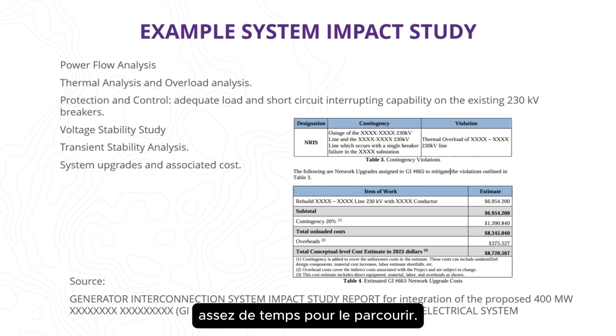I did mention IEEE 1547 and IEEE 2800, for those of you who are members of IEEE. If you're not, I urge you to become one so you can dive into greater detail on these standards. IEEE 1547 applies to DER interconnecting with a distribution system, while IEEE 2800 applies to IBRs, inverters, power control systems, and the like interconnecting with transmission and sub-transmission systems. IEEE 2800 has somewhat more stringent requirements than IEEE 1547, providing more stringent plant-level requirements for bulk system-connected IBRs and focusing on advanced capabilities and grid support, whereas IEEE 1547 focuses more on the individual unit level of the inverter itself.